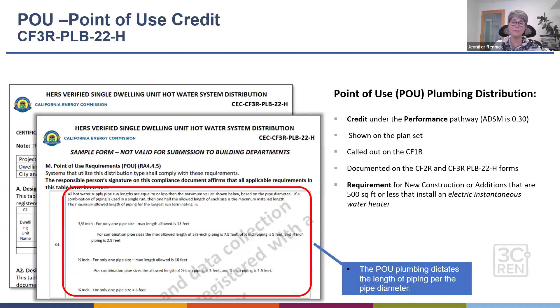This is where architects and plans examiners come in, because somebody somewhere is supposed to show that the length of piping needed, based on the nominal line size versus length for each run, takes the most direct path and stays within these length parameters. Usually that's done directly right from the hot water heater.